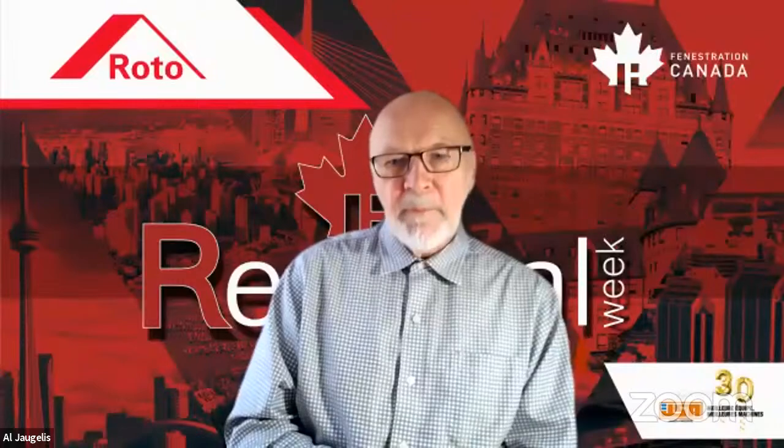Okay, I want to offer up one comment on the comfort discussions that we're having. Historically, and at least in my experience here, the energy analysis programs don't handle shortwave radiation very well. So think about the comfort offsets that you get in your car driving, with the sun shining directly on you. The temperature in the space may be okay, but you're uncomfortable because of that shortwave gain that's directly on your body. Few of the programs actually analyze that. In fact, when they do an MRT, a mean radiant temperature, mostly that's in the center of the space, away from the window. And so critical to that window discomfort question becomes, where are you relative to the window? And are you picking up the offset from shortwave as well as room temperature effects?